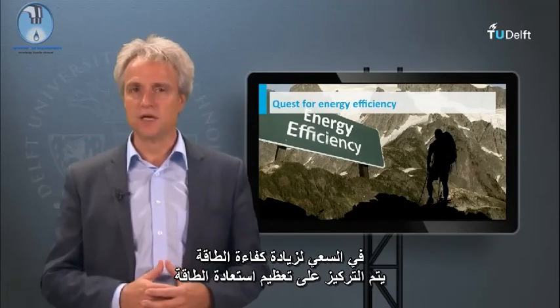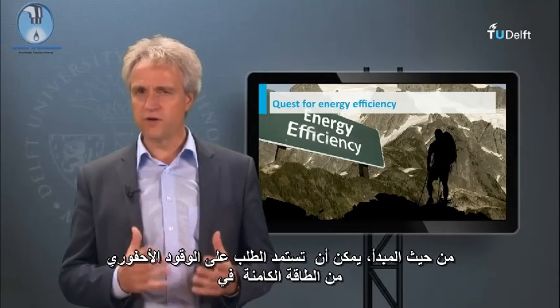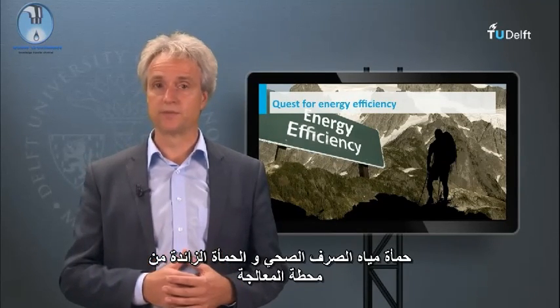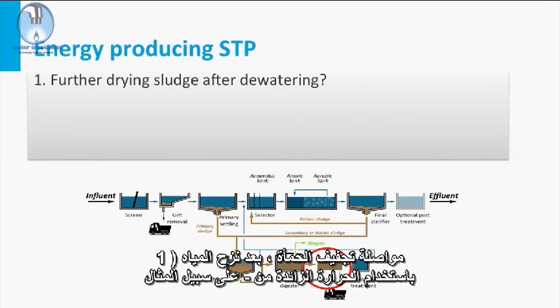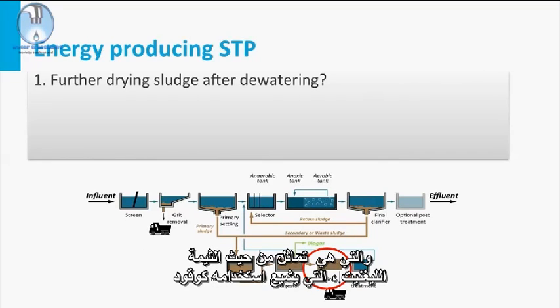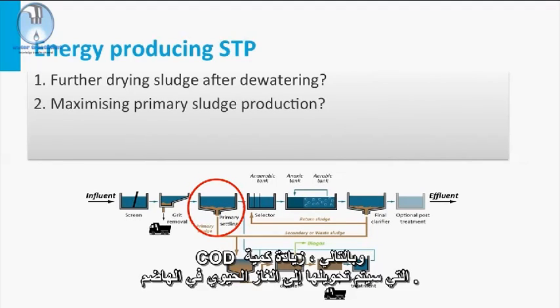In the quest for energy efficiency, a large focus is put on maximizing the energy recovery from excess sewage sludge. In principle, all fossil fuel demand could be derived from the energy bound in the sewage sludge from the treatment plant. Increased energy recovery from sludge could be achieved by: first, further drying of the sludge after dewatering using excess heat from, for instance, the biogas generators. Sludge with a dry solids content of 90% has a heating value of about 10 to 16 megajoules per kilogram, which is in a similar order of magnitude as lignite, commonly used as fuel. Second, maximization of primary sludge production by adding chemicals to the primary clarifier, thus increasing the amount of COD that will be converted to biogas in the digester, while less energy is required for oxidation in the aeration tank.